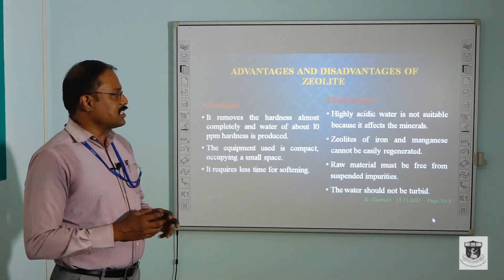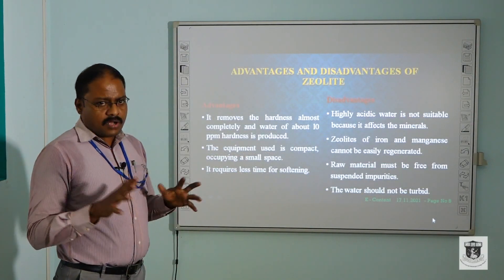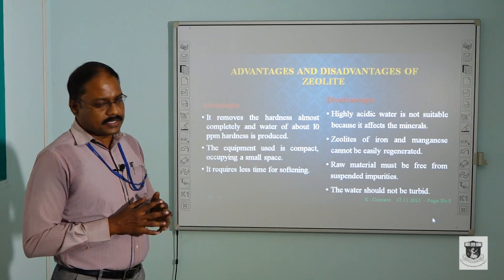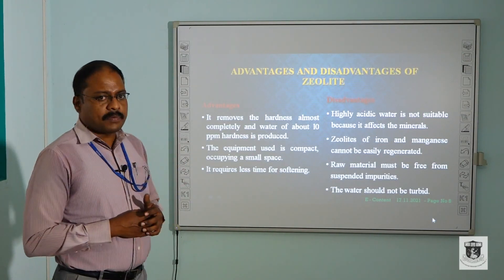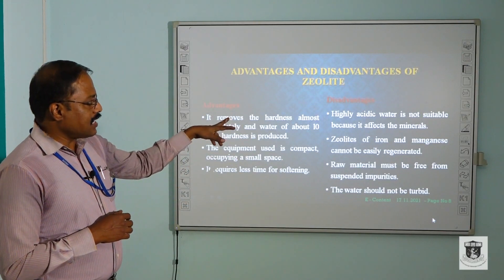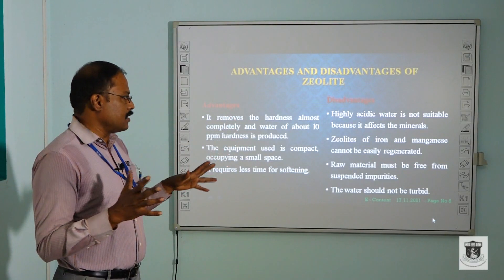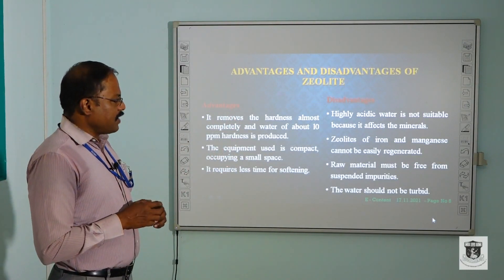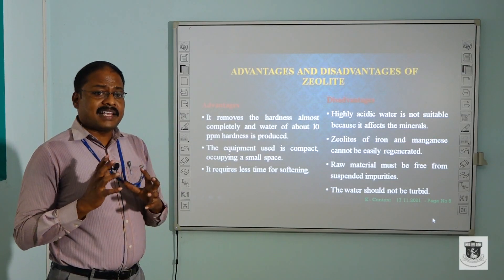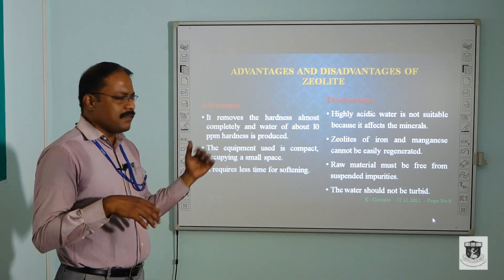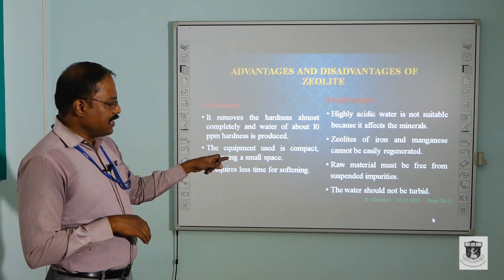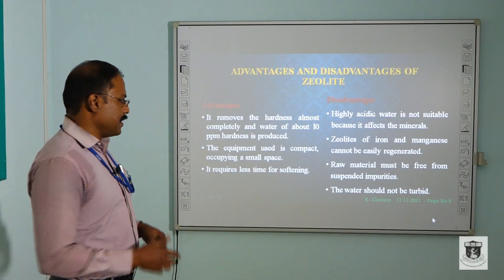Now, the advantages and disadvantages of zeolites. Advantages: it removes hardness from the water — as low as 10 ppm hardness is produced; the equipment used is compact, occupying small space; and it requires less time for softening. Disadvantages: it is not suitable for highly acidic water as it affects the minerals; zeolites with iron and manganese cannot be easily regenerated because these ions cross-link in the zeolite; the raw water must be free from suspended impurities; and the water should not be turbid.